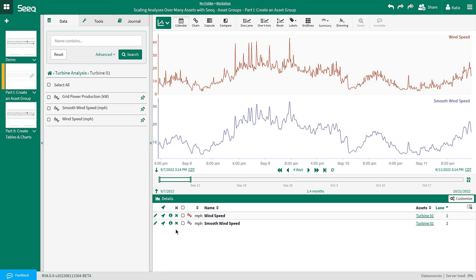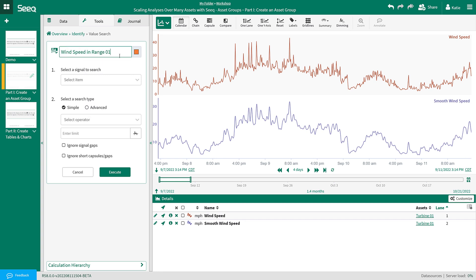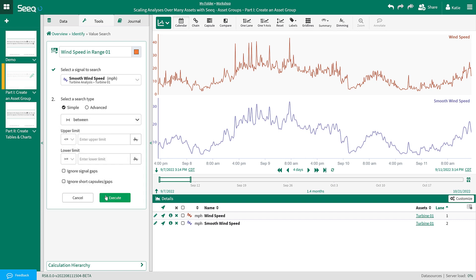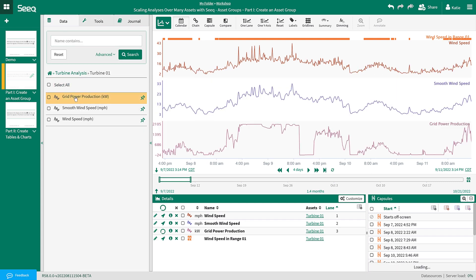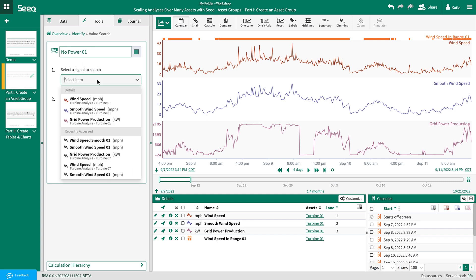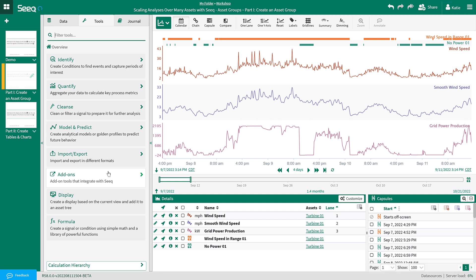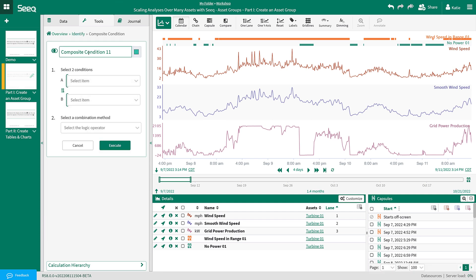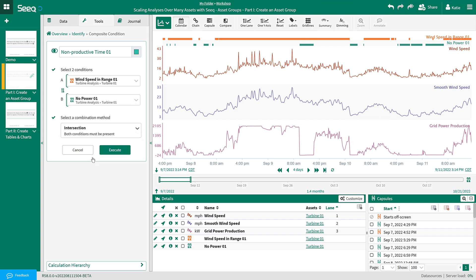Next, I want to create three different conditions. I am going to create them first, then add them to the asset group. Using value search, I will create a condition for when the wind speed is in range — searching the smooth wind speed signal for when it is between 8 and 55 miles per hour. You can see the condition appear at the top of the trend view. Now I am going to add grid power production to the trend from the asset group and use value search again to create a condition for when there is no power being produced — searching the grid power production signal for when it is less than or equal to zero. Then I will use composite condition to find the combination of the two conditions: when the wind speed is in range and the turbine is not producing power. I will call this non-productive time and choose both of my conditions, setting the combination method to intersection.